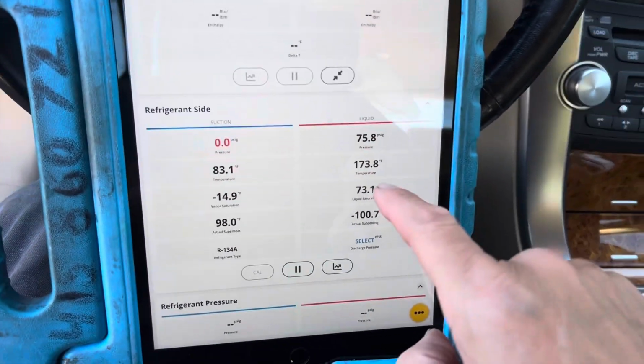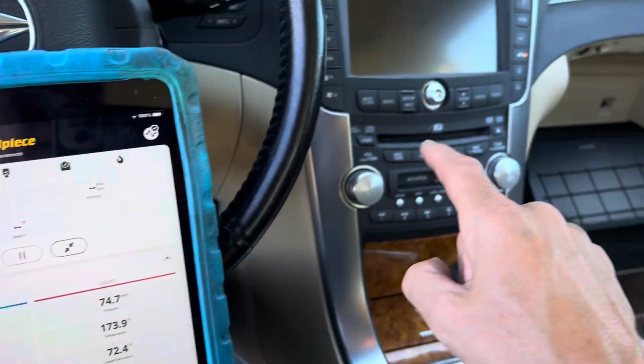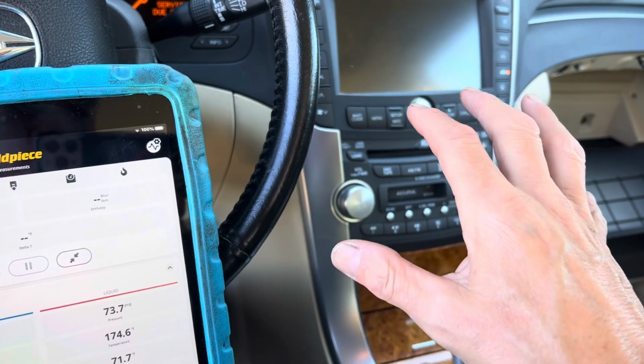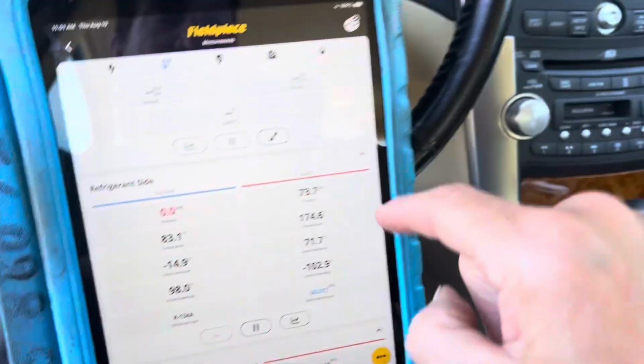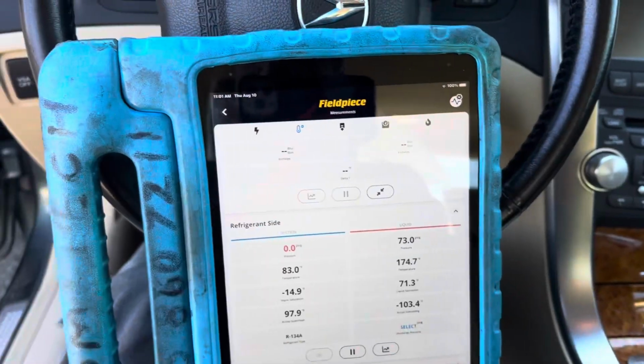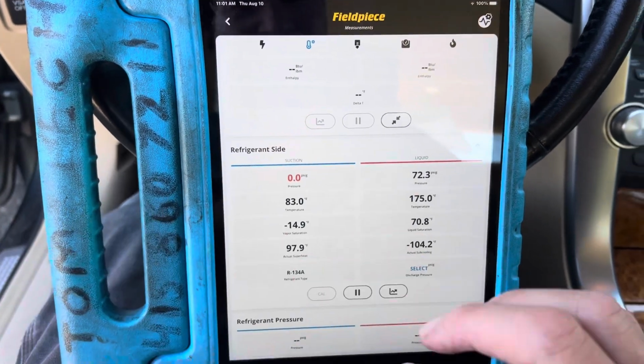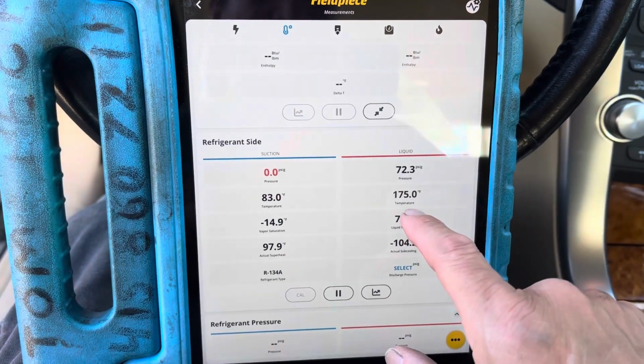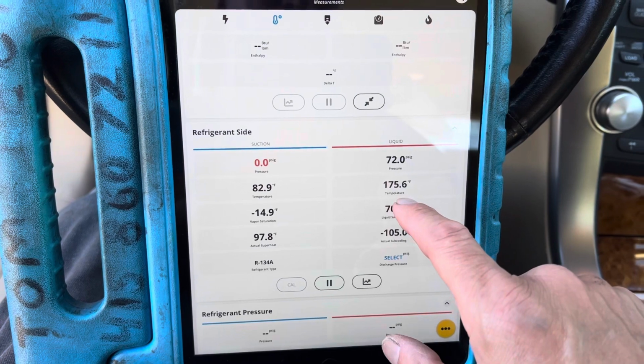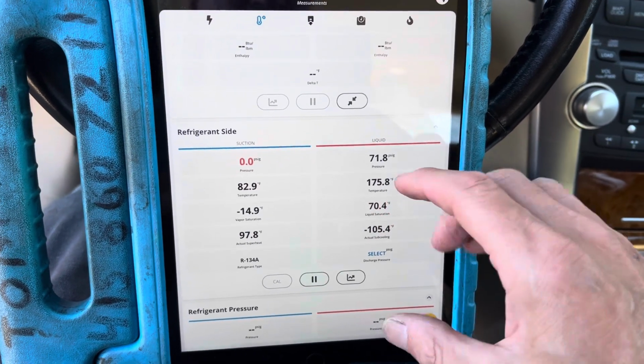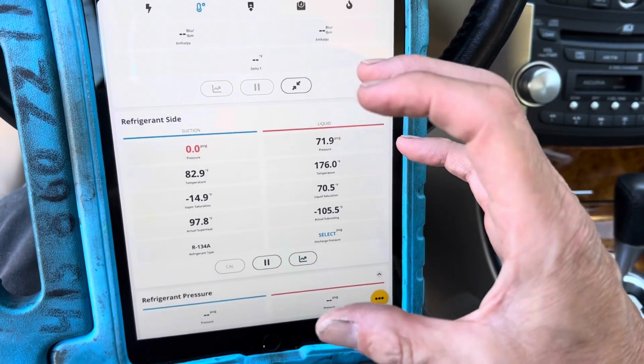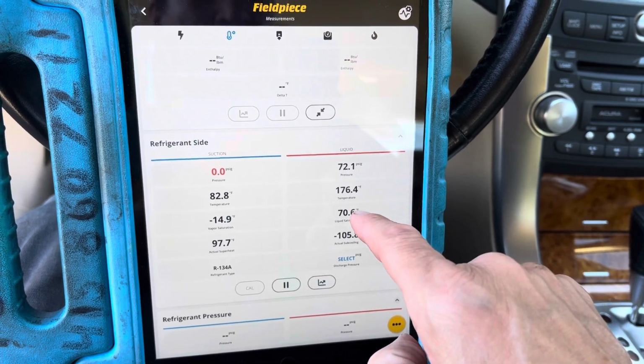Right now in this operation, when the customer was on defrost and they don't know it, or they're trying to use their AC, they're slow, and this is a cold day. It's only like 61, 63 degrees outside right now. 175 degrees is the discharge temperature, and the compressor core and the pistons are starving for oil right now.